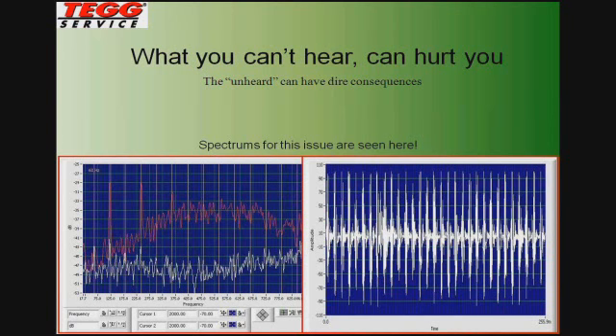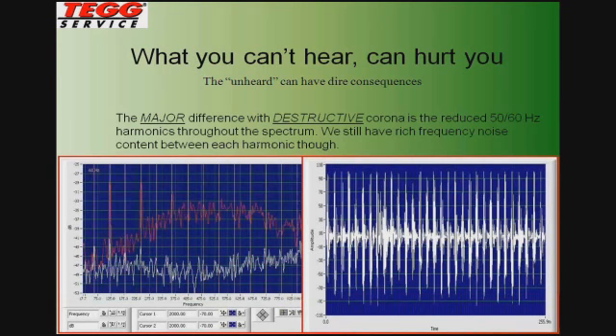So these are a couple of the things I pick out when I'm dealing with systems over 1,000 volts and I believe destructive corona is taking place. So that's what it's pointing out here. Very similar spectrums to tracking. That makes sense because now we have discharges on insulators, and that's occurring on top of the corona, which masks the fault frequencies, but we get greater symmetry in the time domain, as can be seen on the right-hand side here.